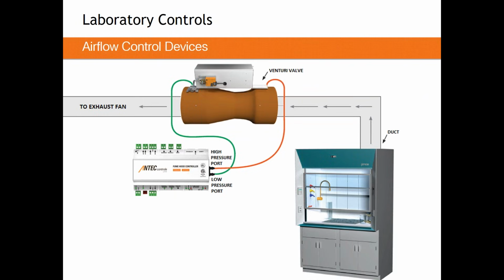That's the first thing we have technicians check when they start one of these systems up, is do you have pressure drop across your device? If you don't have it, don't start your fume hood or your supply or exhaust up. Don't try to balance or commission these systems. Get the pressure in line first and then do the rest of the work. So instead of just a low pressure switch on every single device, which would tell you whether you have airflow or not, we put a real true transducer on there. So you know if you have just enough pressure or if you have happily 1.5 inches or something like that.